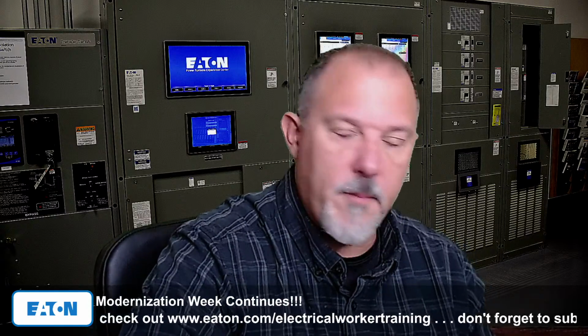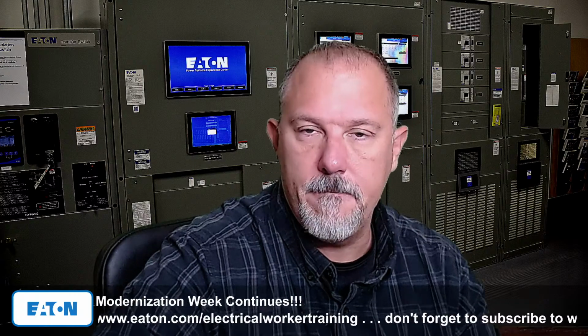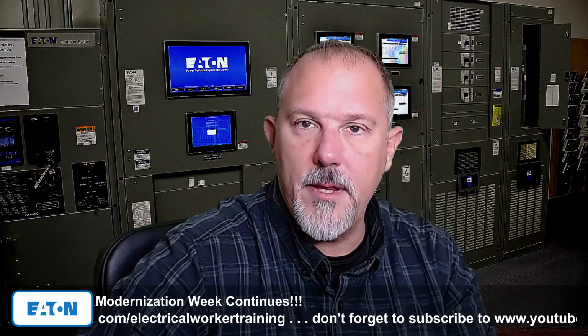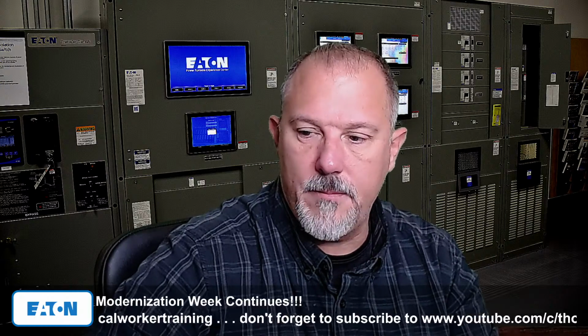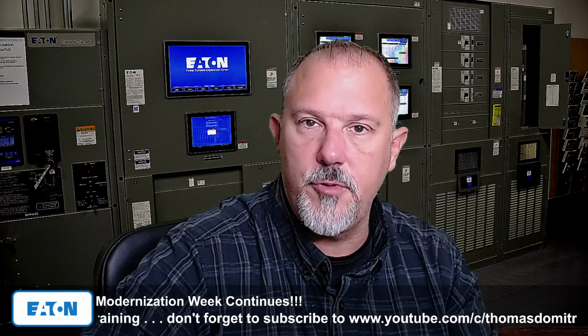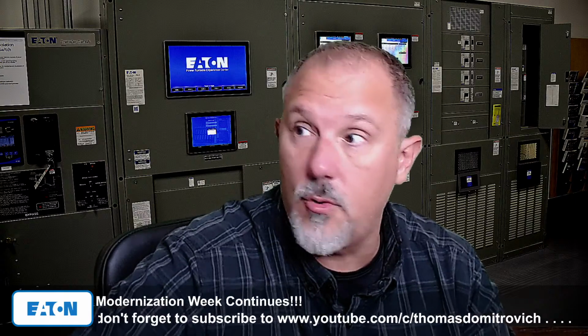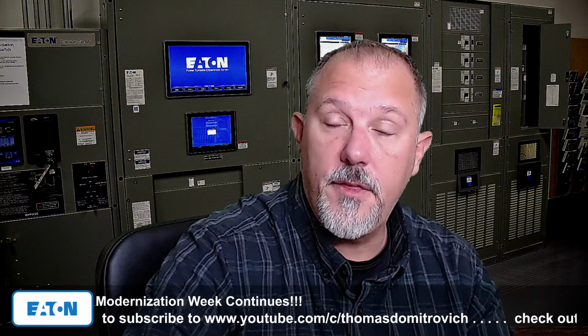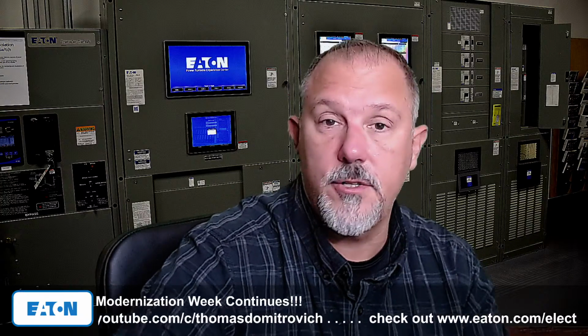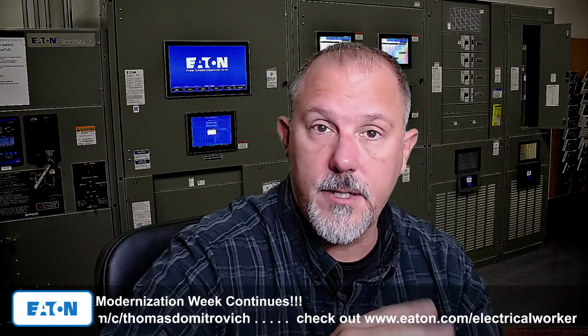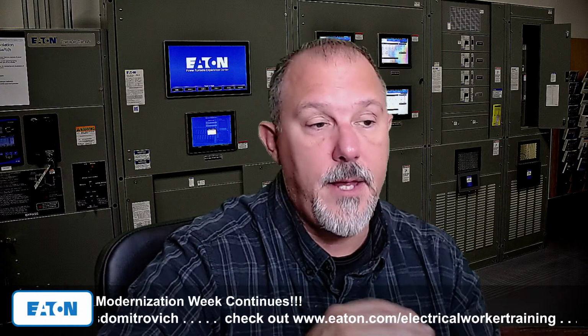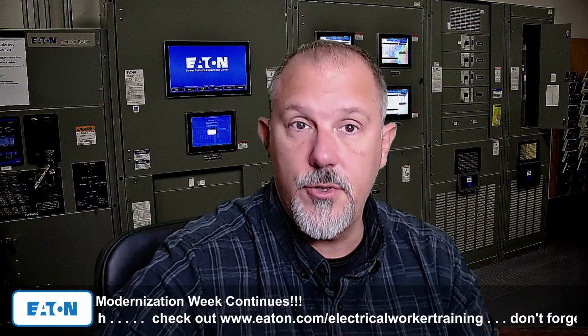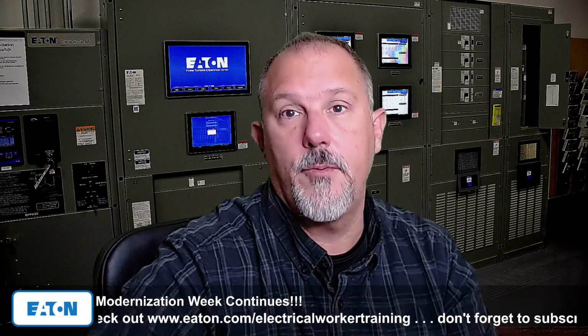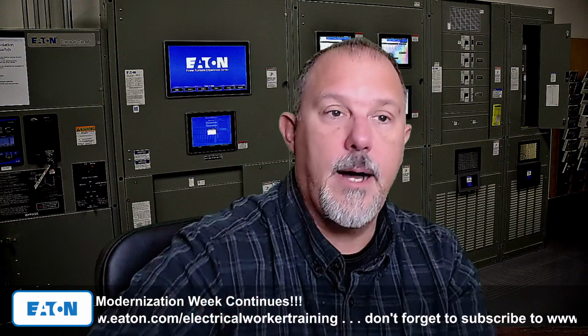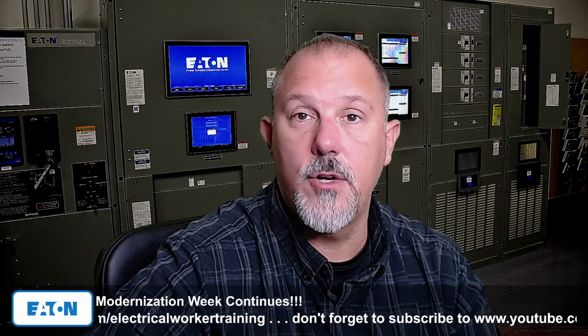If you're required to worry about it per the National Electrical Code, then you've got to address it. If you want reliability, if you have an outage, if you want to maintain a reliable power distribution system for other reasons other than the National Electrical Code or safety, it could be money for you, then you need to consider that and do that evaluation. I know too many engineers who do not do that evaluation, who do not compare overcurrent devices with any fault current. They hide everything below 0.1 seconds, don't calculate fault current, look for separation of curves, and they think, I'm good to go. You are, if that's your goal.